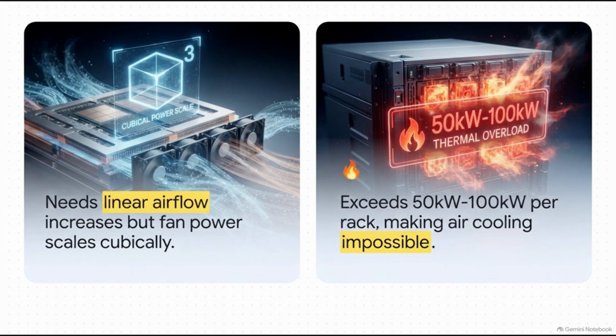But here's the real killer: while your airflow needs increase linearly, the power required to run those fans scales cubically. It creates a vicious energy consumption spiral that rapidly gets out of control. It just becomes economically and practically impossible.